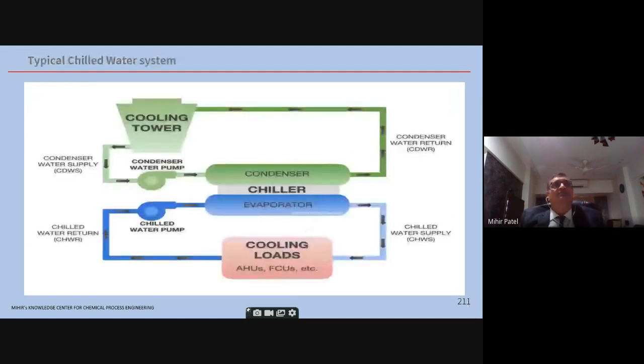Typical chill water system. A brine system also can be the same. Chill water is normally kept at about 6 to 12 degrees supply and return temperature. A brine system normally has methanol, or you can have MEG, monoethylene glycol, as an antifreeze. So I have operated brine systems at minus 20 degrees supply and about minus 8 to 10 degrees as the return temperature from the brine. So as you can see, the top is the cooling tower system. In the middle you see the chiller, which is the package item. At the bottom is the chill water circuit.